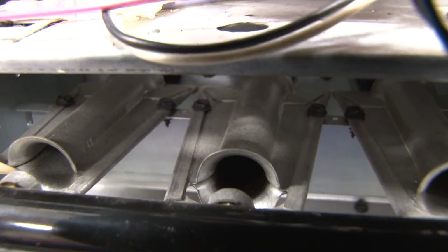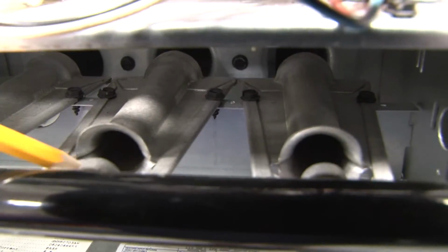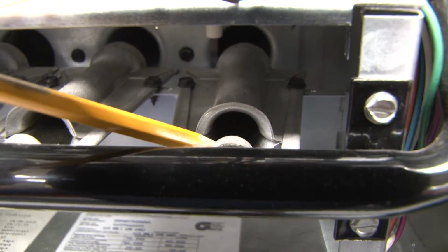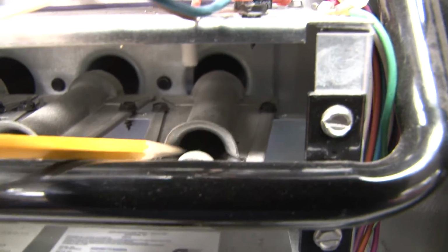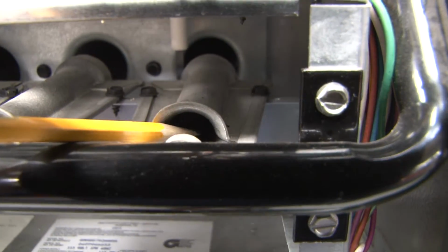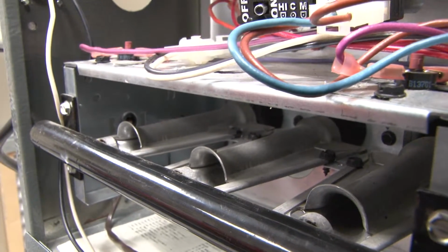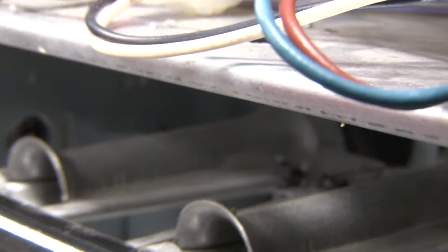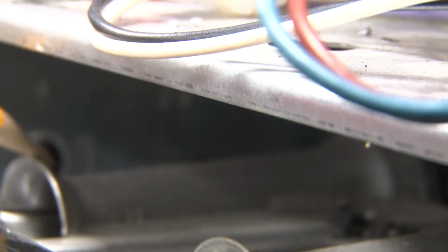It will create 3.5 inches at the orifices, and that gas will be injected into the burner. This burner is basically a Venturi type burner, where you can see, I'll zoom in a little bit so you could probably see it a little bit better. The construction of this burner, it starts out very large at the opening, and it will reduce down to cause a restriction, which will cause the velocity to increase, since any restriction in airflow will cause the velocity to increase.